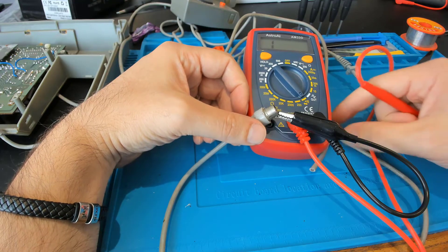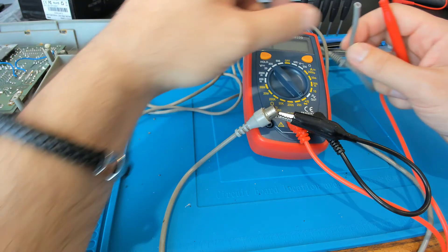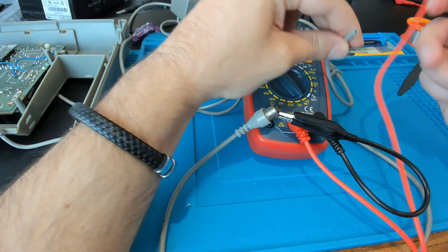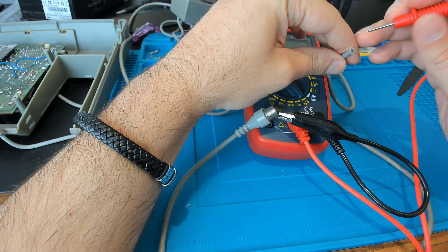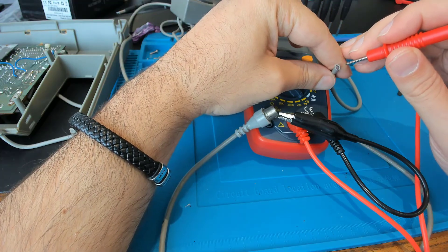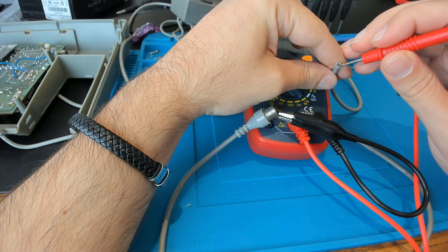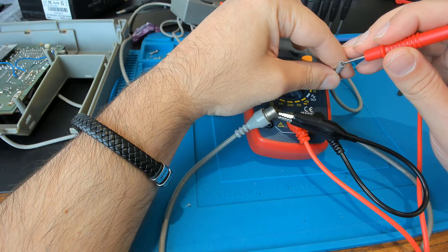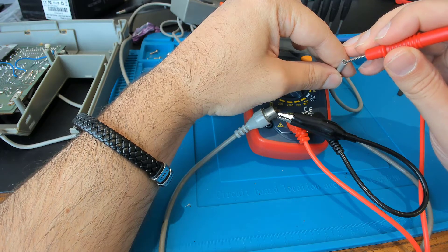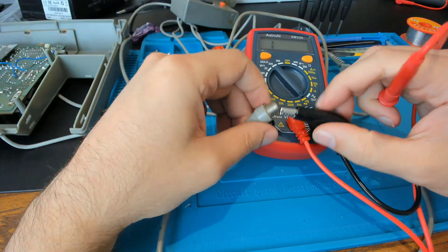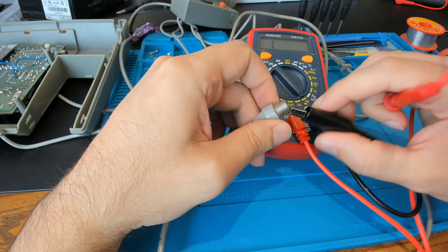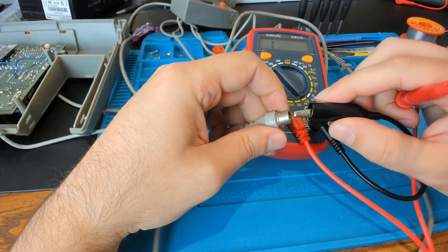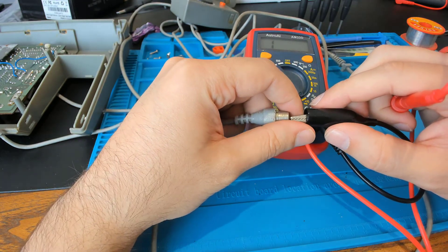Then I want to check that the mesh cable on the outside is also making a continuous connection. So I place one probe on the outer ring of the connector and the other probe on the braided shield on the other end. Or if there was a connector on the other end, I'd place the probe on the outer ring of that other connector. Again, that beep sound tells me that there's a continuous connection of that braided cable on the outside from one end to the other.